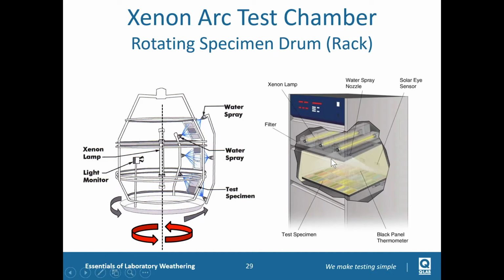Okay, let's see the difference between them. For this one, the lamp is in the middle, and your specimen will hang on it like a drum, right? On the wall. It will hang here, and there's a light monitor, and there are water spray nozzles. So the rack will rotate around the lamp, okay? And in our chamber, it's a flat array, a tray underneath the lamp. We have 3 lamps in our XE3. And we have water spray here, we have light monitors here, specimens, everything is here. What the rotating drum has, we have in our flat array chamber.